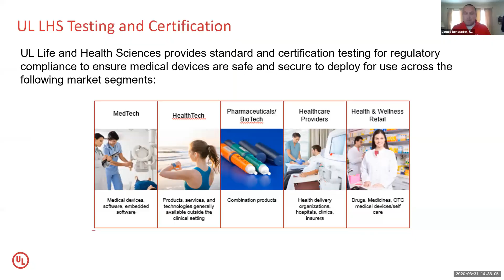The group that I work in for Life and Health Sciences at UL, we do testing and certification work. So we're the ones that actually come along and use these relevant standards that you'll see referenced in the EUA documents to do an evaluation to understand whether the device is safe and effective. When people typically come to UL and they think about these different standards that are out there, a lot of times people have the understanding that the standard is really looking for your basic safety, your electric shock and fire protection items that they may be used to seeing if they've done work on other products. However, in a lot of the medical standards for electrical medical devices, we'll get a lot more, and they'll actually get into whether the device is effective. And that can kind of lead into why in the EUA, they're still talking about seeing information to show compliance with these relevant standards. Next slide, please.